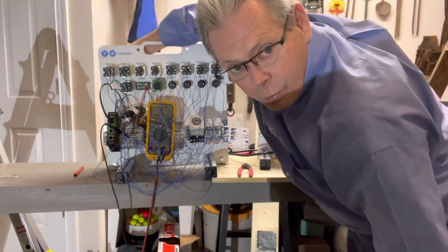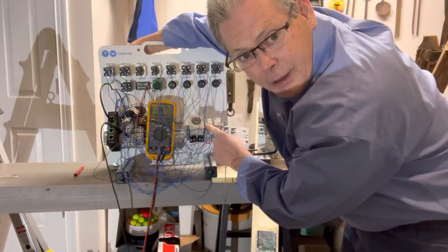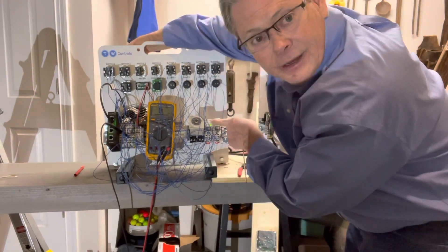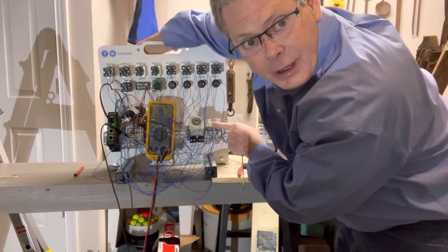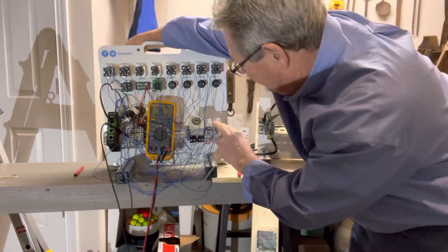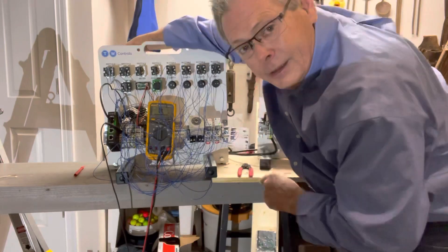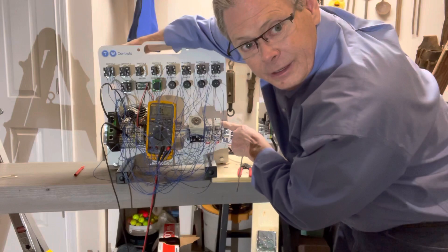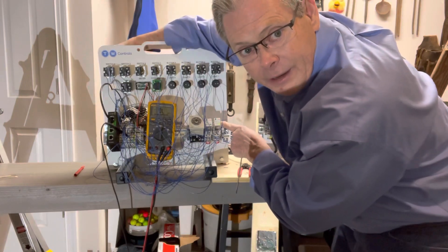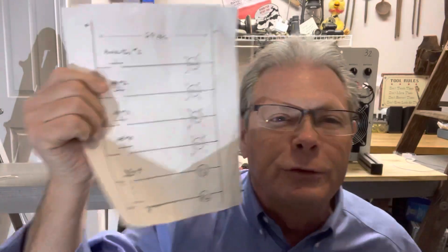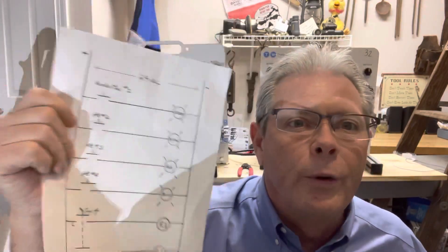Now, this fourth switch up here, when I turn the top to the left, R1 should come on. See it? See the little light? Came on. Turn it to the center, they're both off. Turn the top to the right, it comes on. Right there. See it? Left. Right. That works just like this print. That's what we've got to make it do.